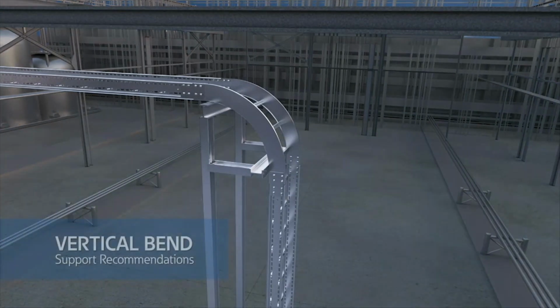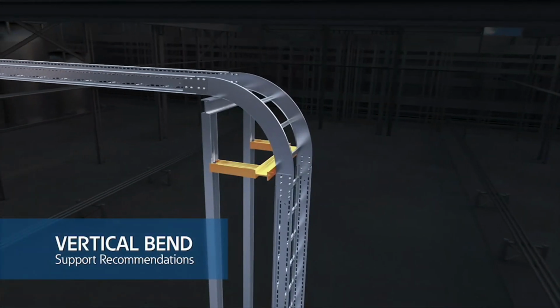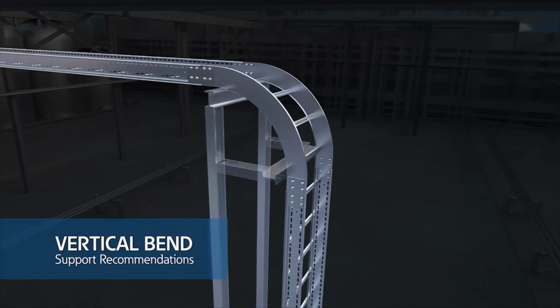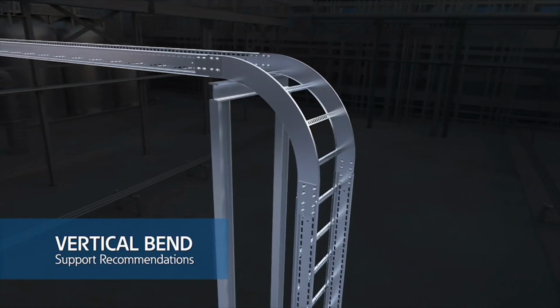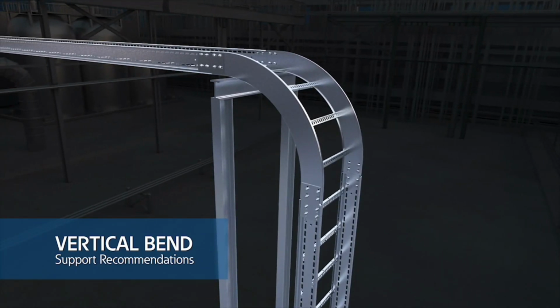For vertical bends, the B-Line series system requires the use of only 1 support per fitting, rather than the 2 recommended by NEMA. This single support can be placed at any point along the fitting.